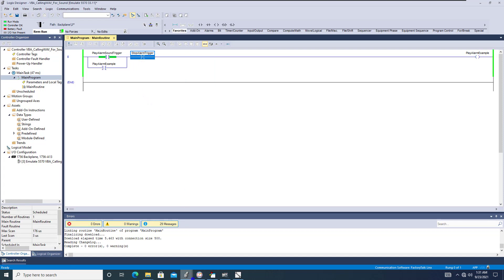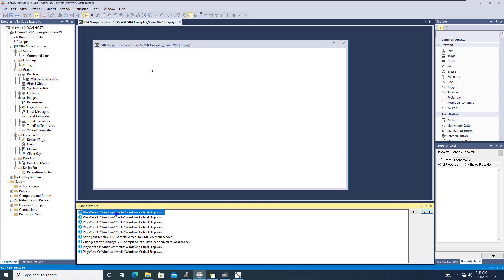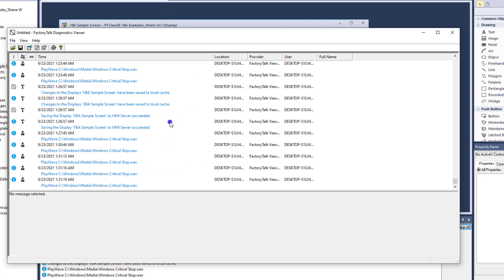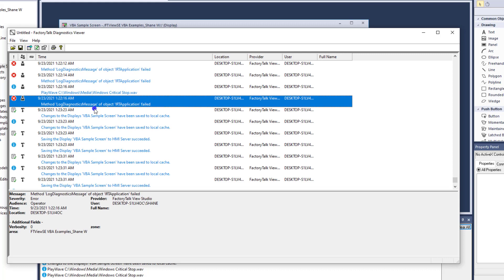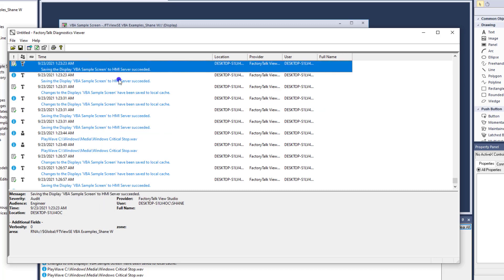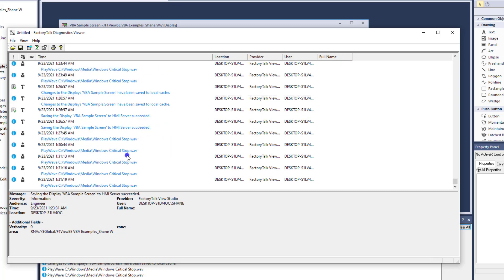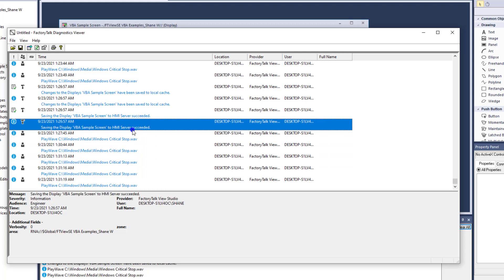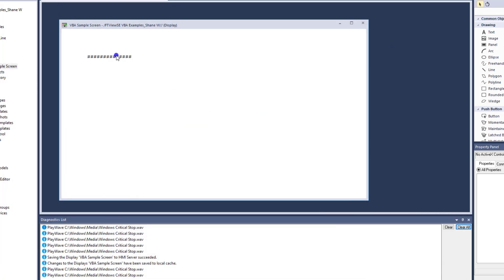No matter how many times I trigger this, you can see it's going to play each time. In the diagnostics right here on the very bottom of the screen you'll see that. There are also two diagnostics you can pull up — the diagnostic viewer. When you're troubleshooting any kind of HMI system, it's always best to use the FactoryTalk Diagnostic Viewer to see exactly what's happening. If you had some kind of error in your VBA code, you can go in and fix it. All the successful events are right here — you see all the play waves that happened, when they happened, with timestamps, who did it, what the provider was.